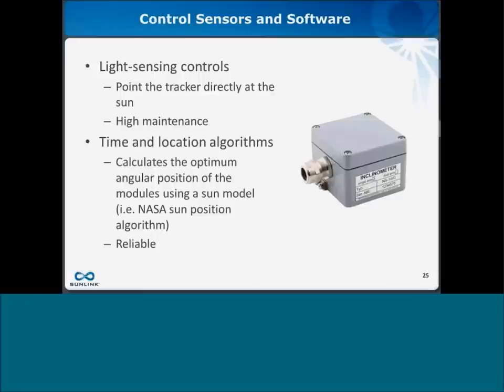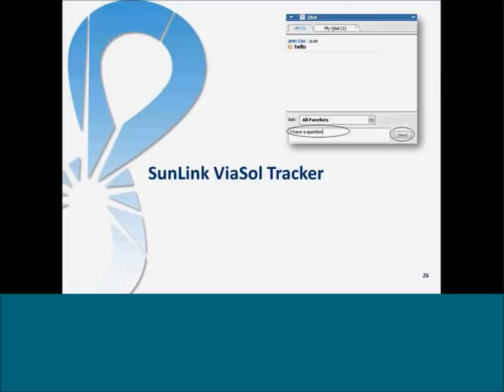It seems like the whole industry now has moved to an inclinometer type control feedback, where it measures the position of the tracker row. Then the PLC, or the custom control board, calculates the correct position and sends a signal to the actuator system to move it to where it needs to be. It's proven to be a fairly reliable way to run a tracker, and that's mostly what you're going to see out there in the market these days.